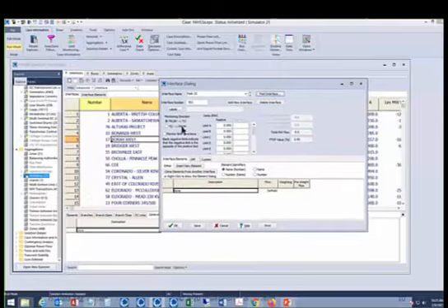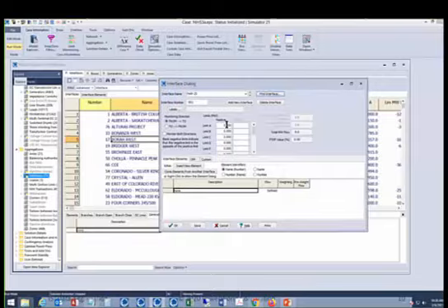But yeah, then normally this is the monitoring direction for the whole interface. So this is like, which end do you look at for the flow? The flows that are looked at in an interface are always megawatts. Whereas lines, the limits could be MVA or they could be amps, but with interfaces, they're always megawatts. So yeah, we'll just leave that as from to to.